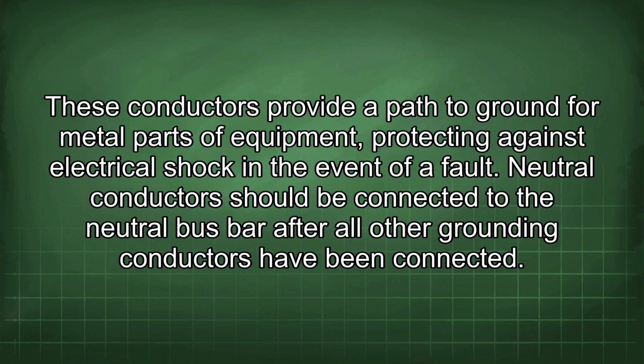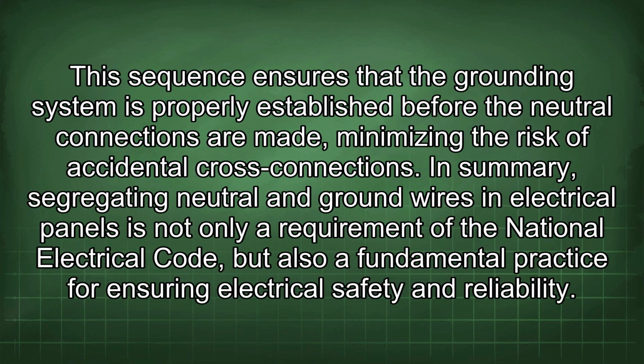Neutral conductors should be connected to the neutral bus bar after all other grounding conductors have been connected. This sequence ensures that the grounding system is properly established before the neutral connections are made, minimizing the risk of accidental cross-connections. In summary, segregating neutral and ground wires in electrical panels is not only a requirement of the National Electrical Code, but also a fundamental practice for ensuring electrical safety and reliability.